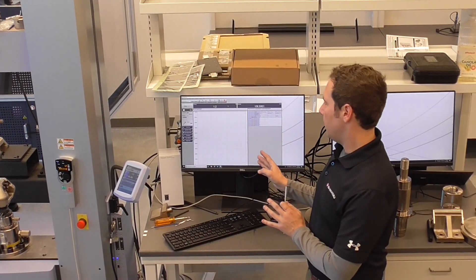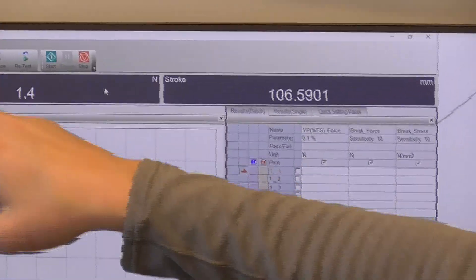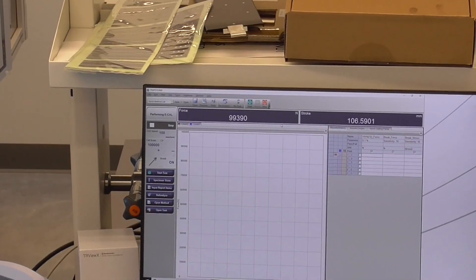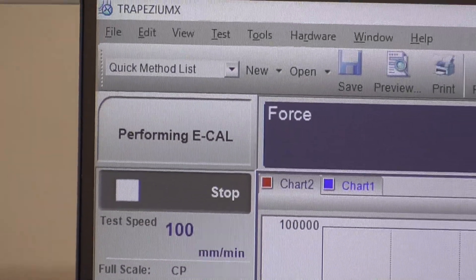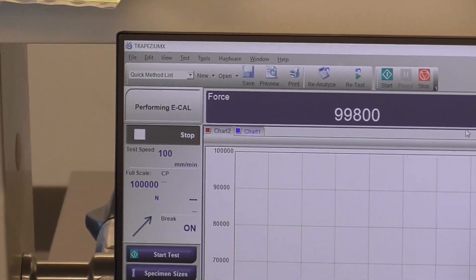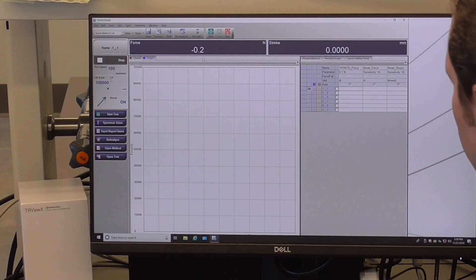So, right here, here's our testing screen. So going from top to bottom, you have some test controls up here. Start and stop. Save, preview the test, information. Here are your sensor outputs right here. Like I was saying, you can calibrate from the touch panel right there. Or you can do it right here. Right click. Calibration. It'll perform the calibration process. It takes about 30 seconds. And essentially, like I said, writing the extensometer data to the frame itself. Also, from here, we can zero our stroke. Alright, what else do we want?